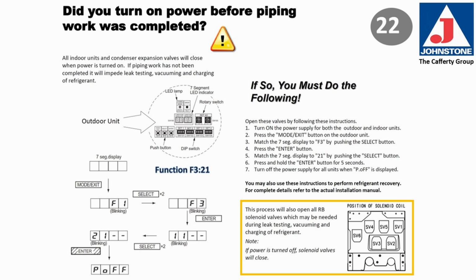This process will also open all of the RB solenoid valves, which may be needed during leak test, evacuation, and charging of the system. If you power the system off, the solenoid valves will close. They are powered open and they fail to the closed position.